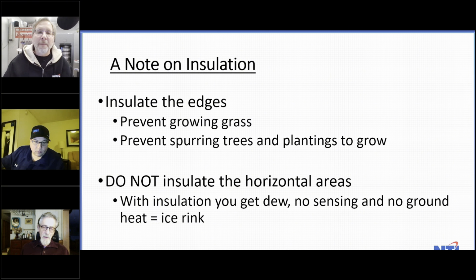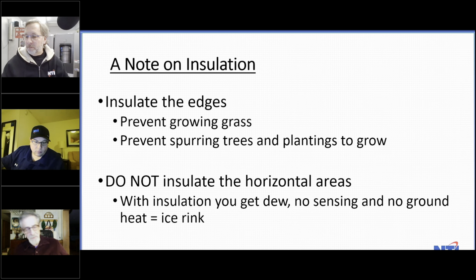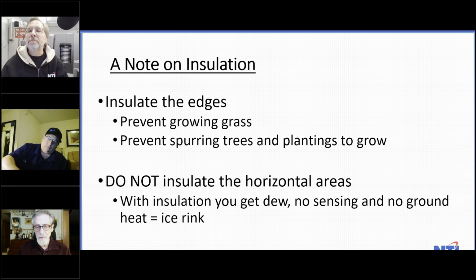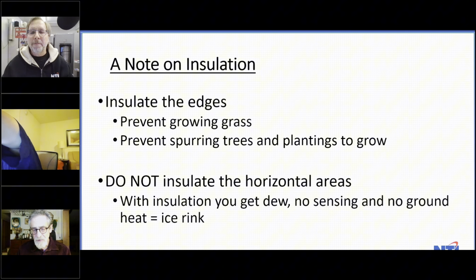I might offer one exception to that, Steve, if you don't mind. Sure, Ted. In that category 3 system, that's the one where you want it clean and dry all the time. Insulating it underneath, because you're going to have the heat on virtually all the time, is not a problem. But understand that you're also putting 250 BTUs or more per square foot constantly, so that's a pretty hefty system to operate.